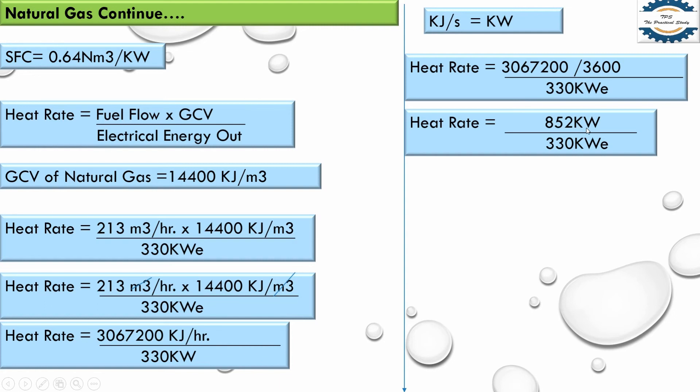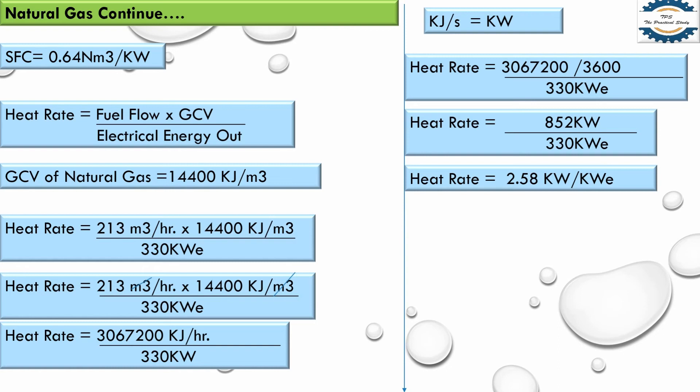So 852 kilowatt is the thermal energy into the generator and 330 kilowatt is the electrical energy output from the generator. Dividing these values, we get a heat rate of 2.58 kilowatt per kilowatt electrical output.